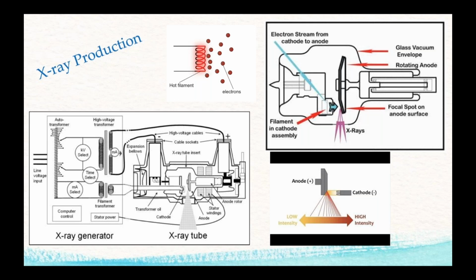But you got to understand, with the advent, when we went from film to CR and now to digital, we're full digital now in most cases. The sensitivity of the electronics in those are so tight that we don't need the amount of energy we used to have to darken film. So when we used to have an exposure of so much mAs at so many seconds, now we're down to 50 milliseconds, 100 milliseconds. So we're only actually making radiation off the anode for that little bitty time frame. And we're still capturing all the data. In fact, we're capturing more data now on digital plates. There's just all the information is there.